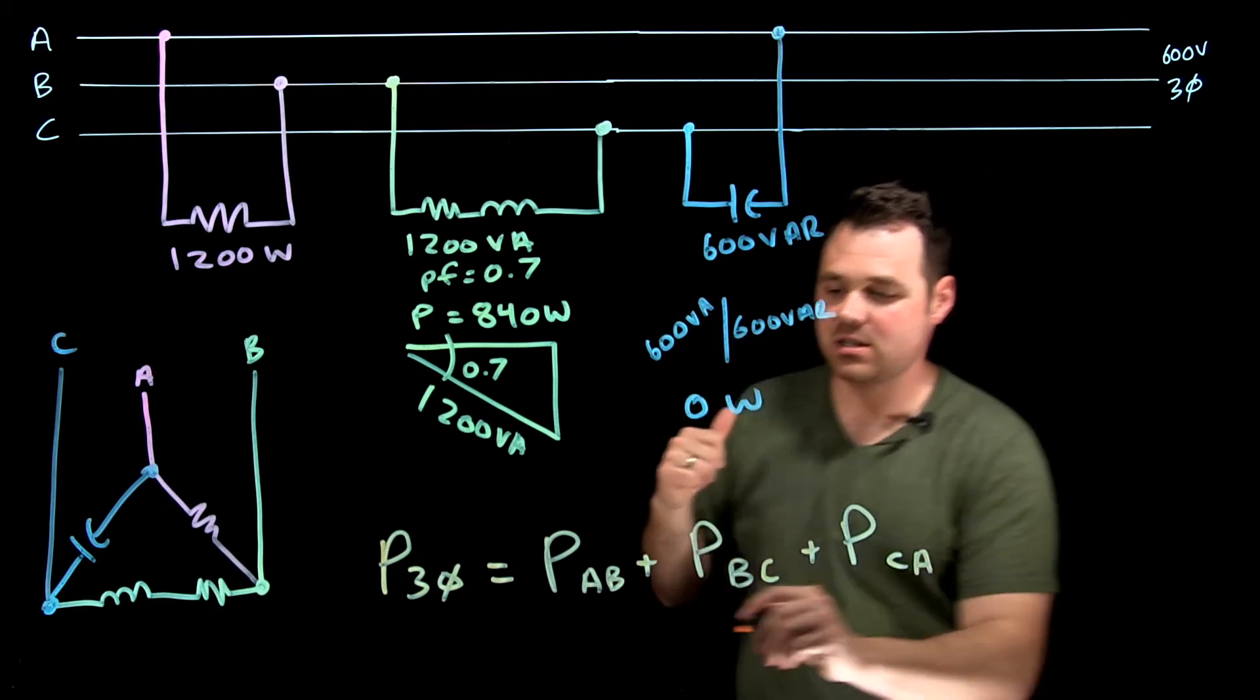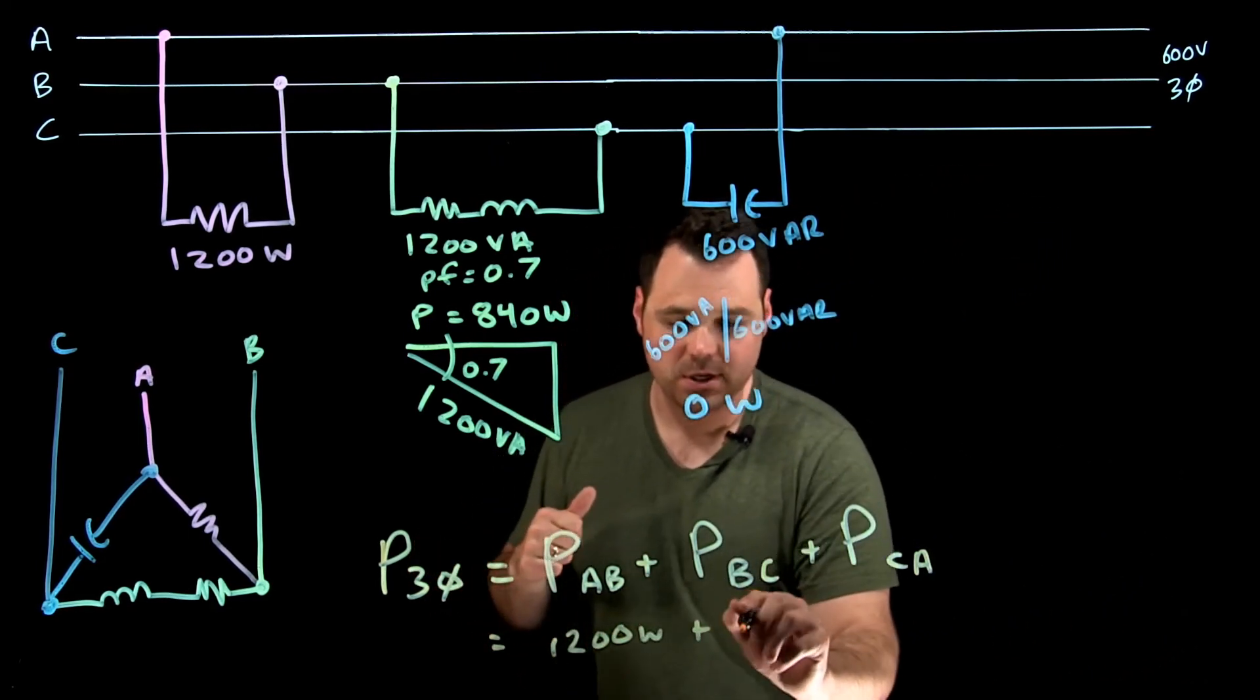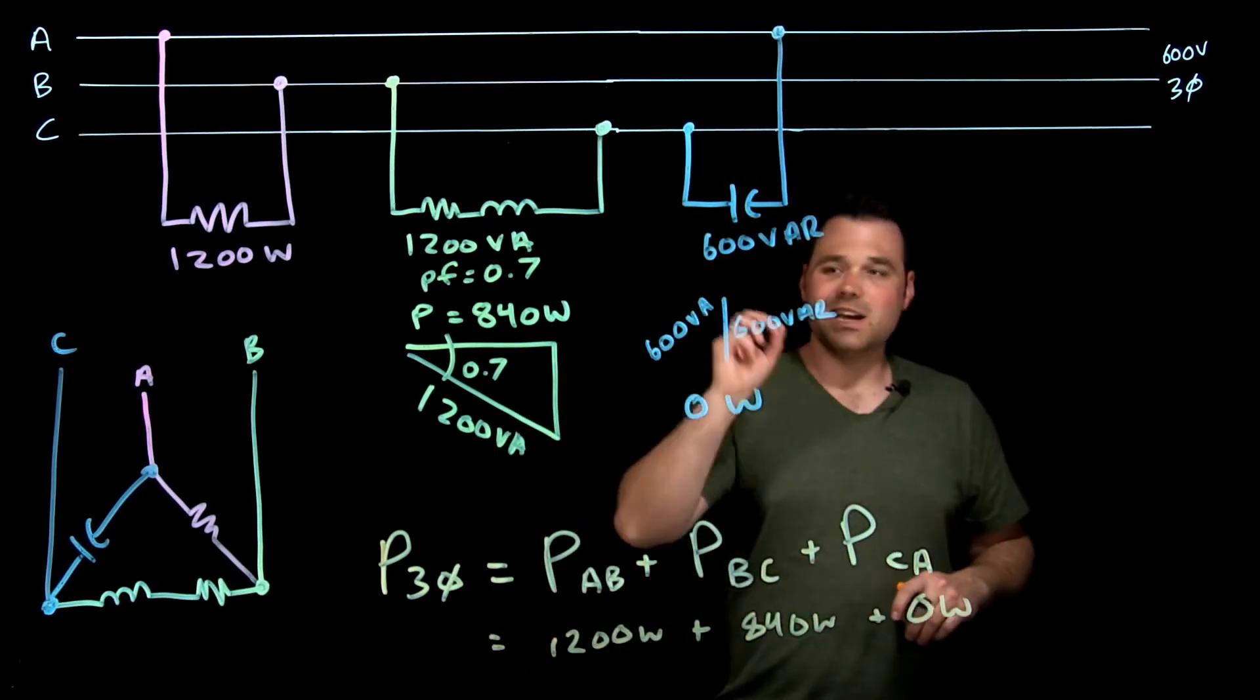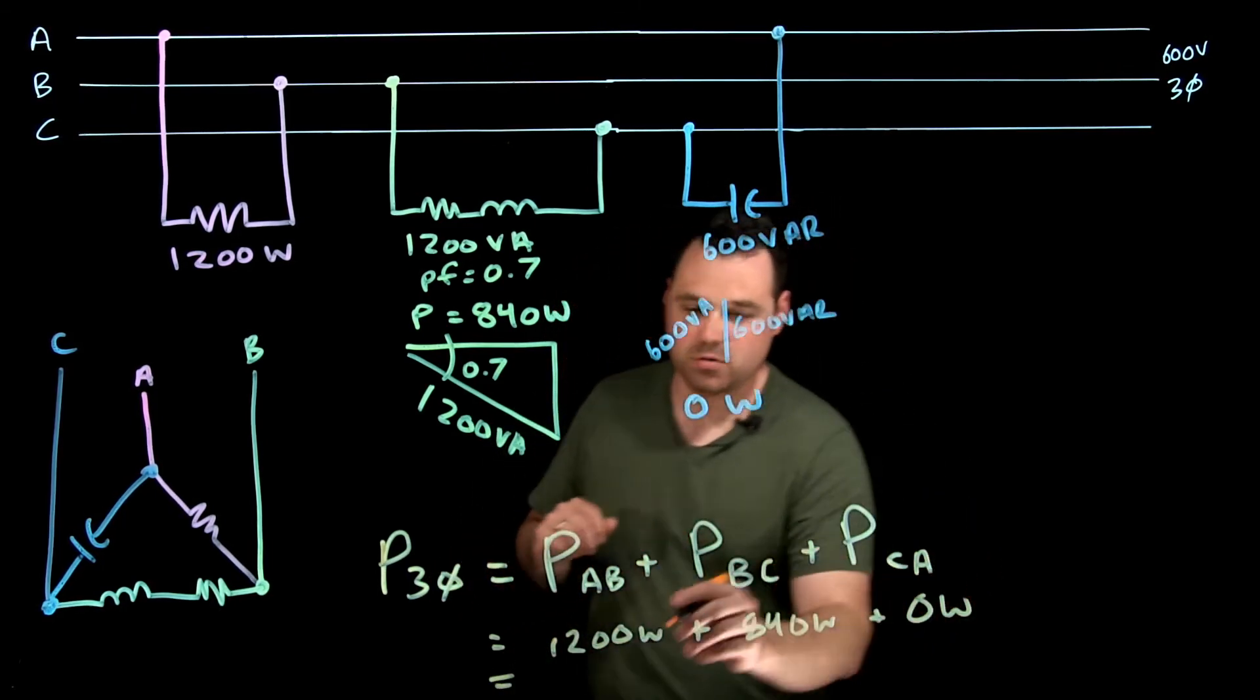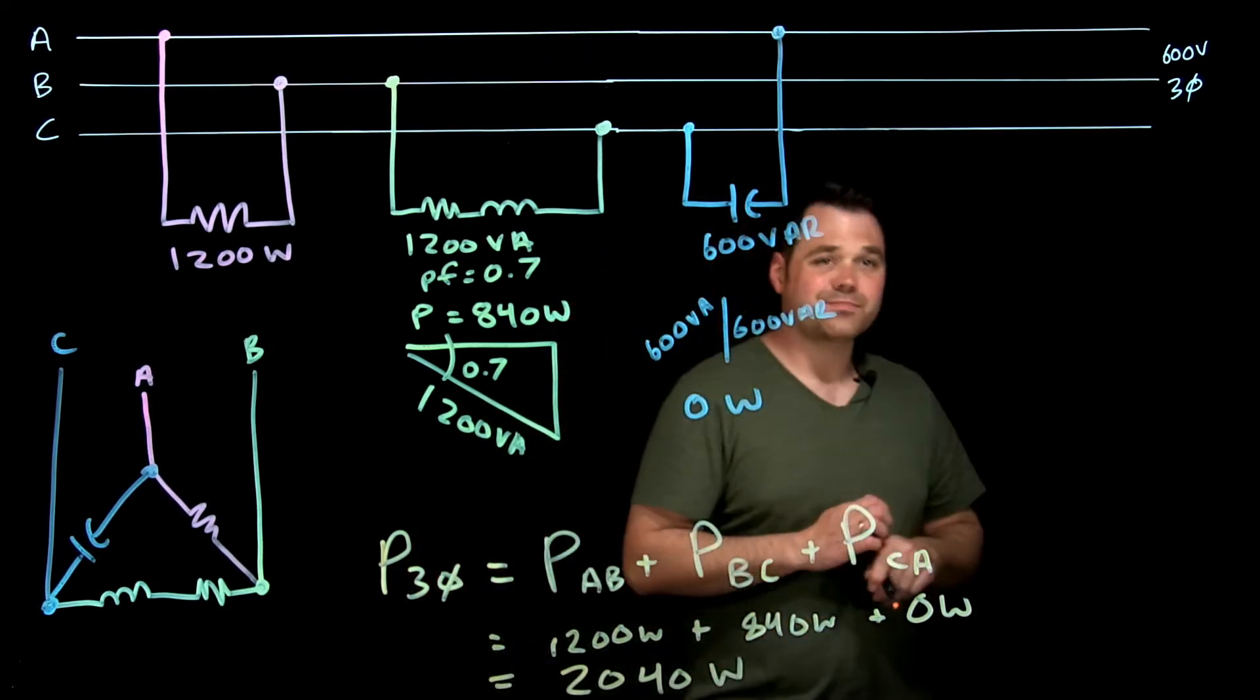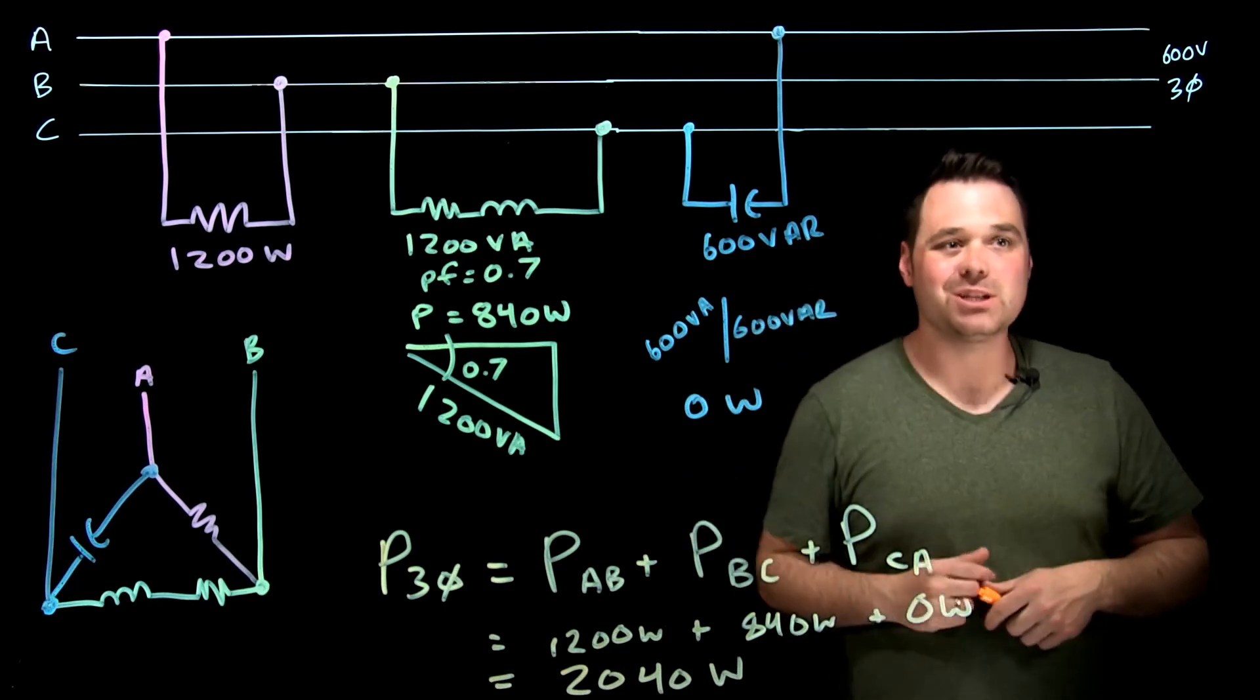So in our case, we would be 1200 watts plus 840 watts plus 0 watts. So at the end of the day, our calculation comes out to around 2040 watts. That's how you would calculate the three-phase power in an unbalanced load.